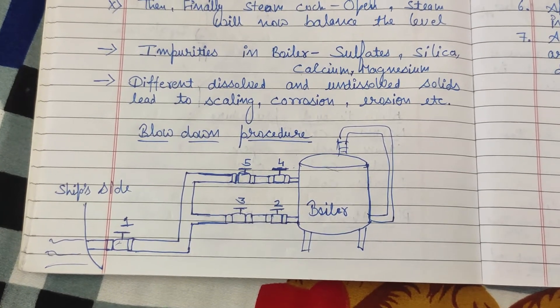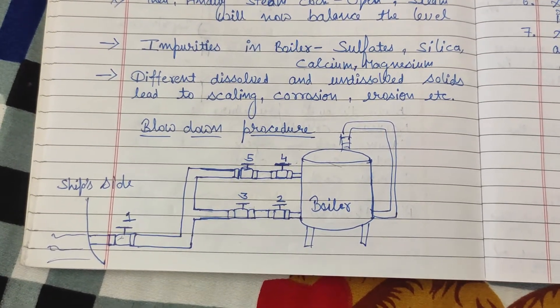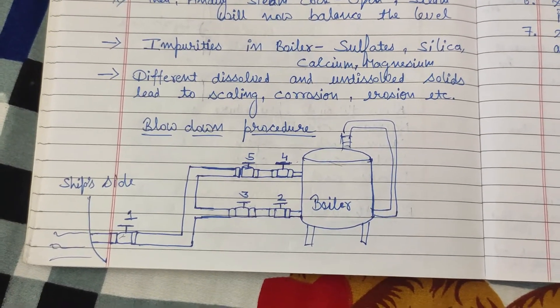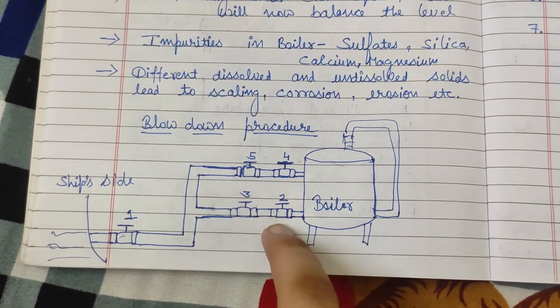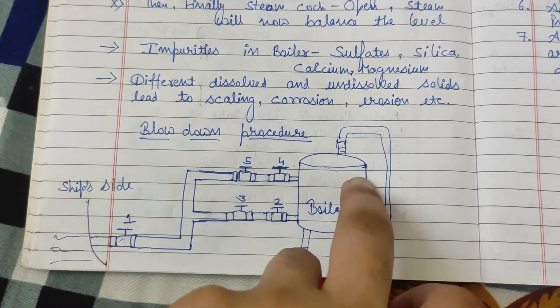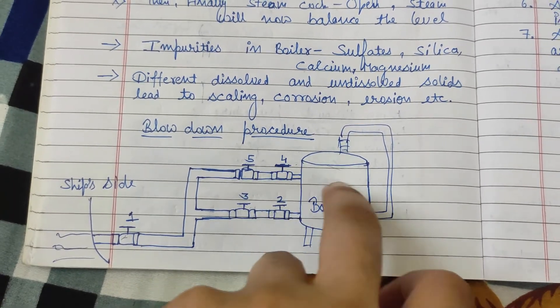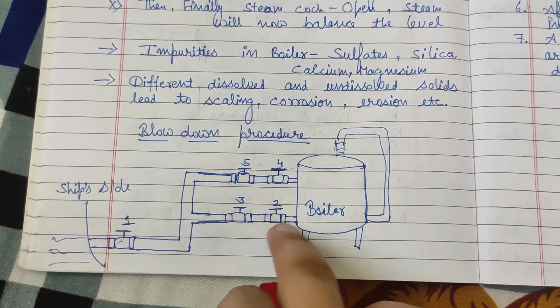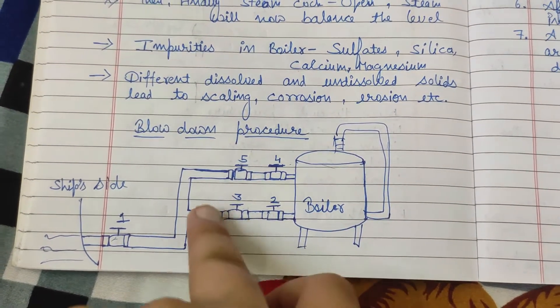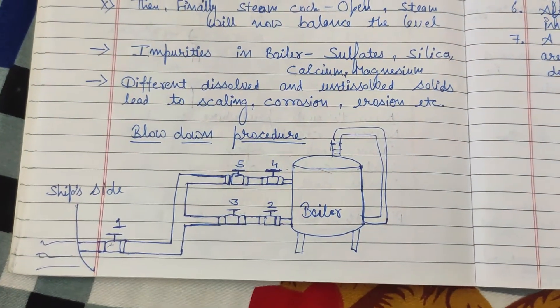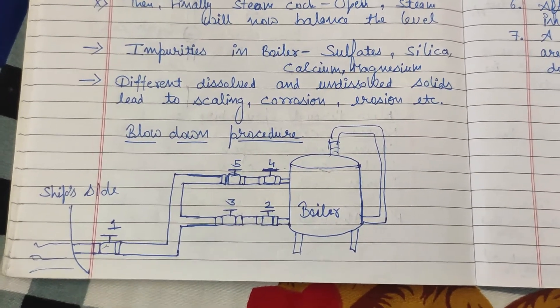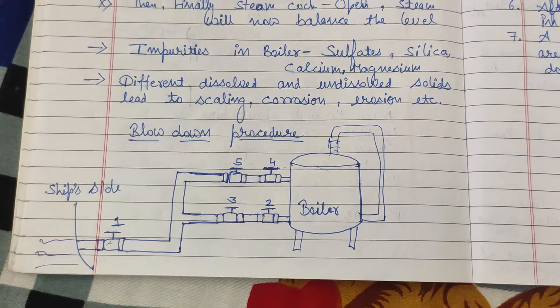The procedure is the same for both bottom blowdown and scum blowdown. There are five valves: the first is the ship side valve, the second is the scum blowdown valve, which is present at the water level of the boiler. The bottom blowdown valves are present at the bottom of the boiler. Two valves are provided for each — both for scum blowdown and for bottom blowdown.